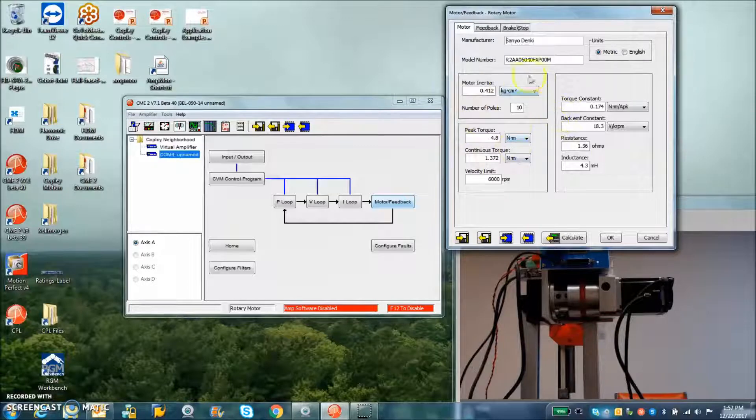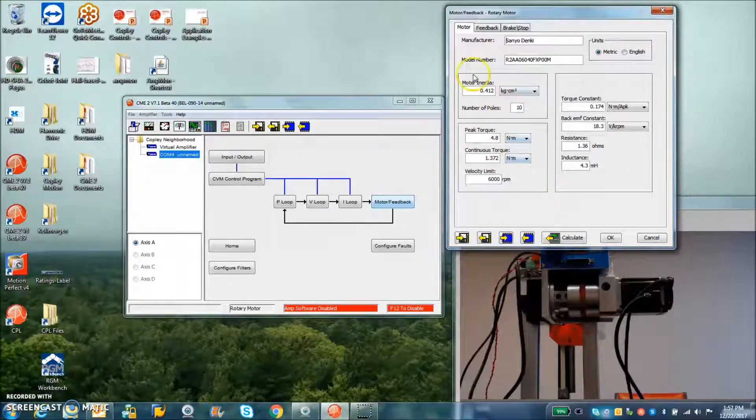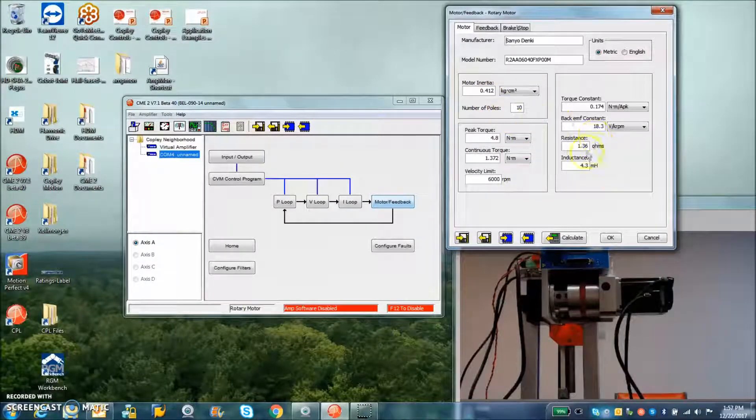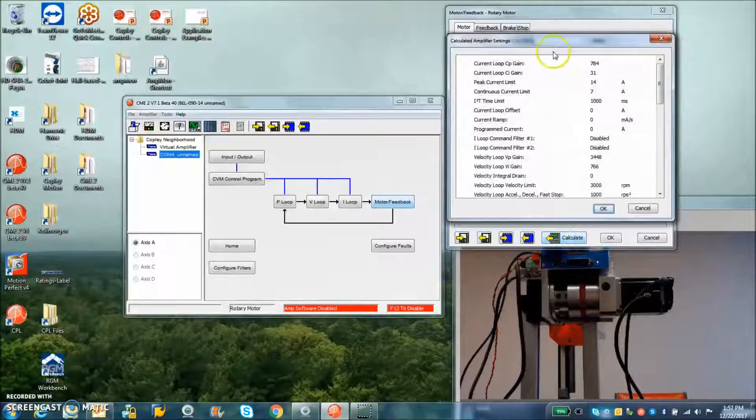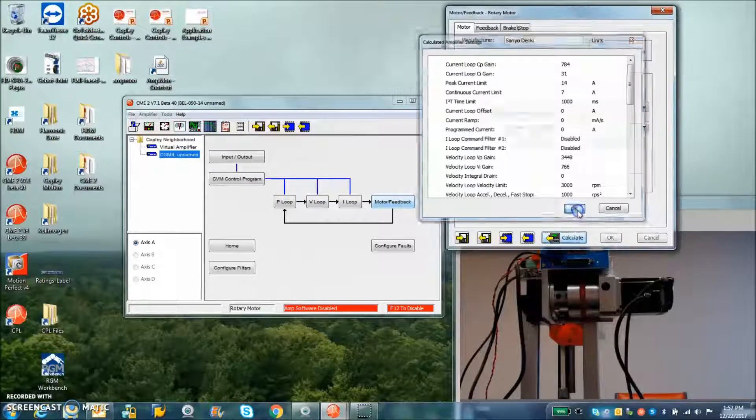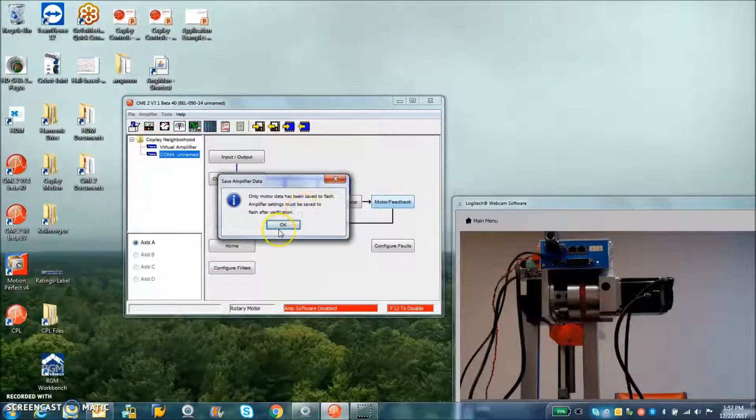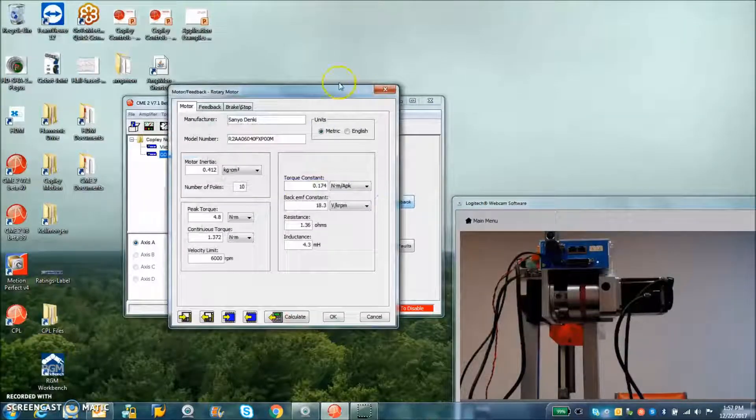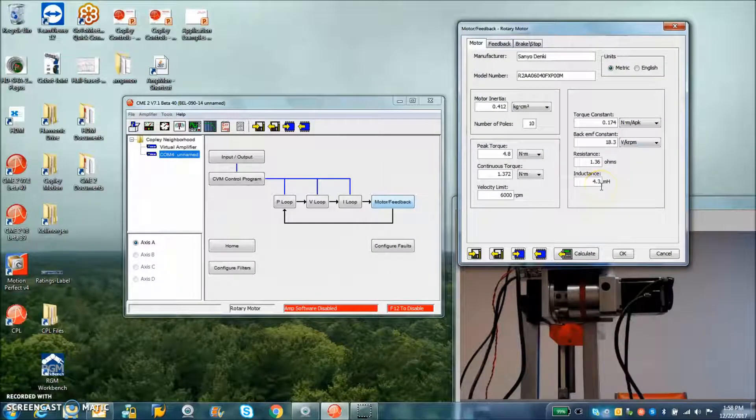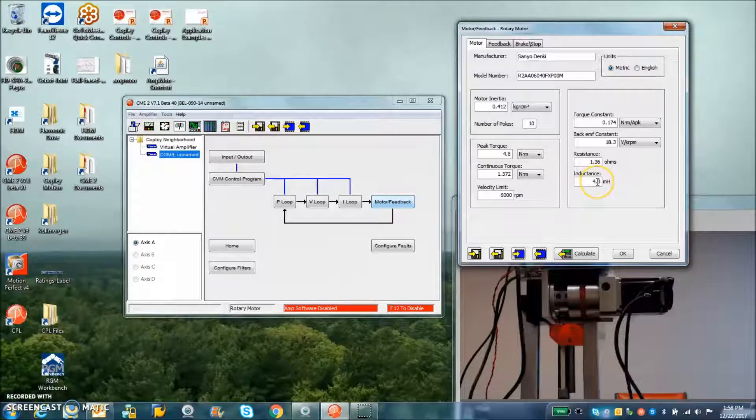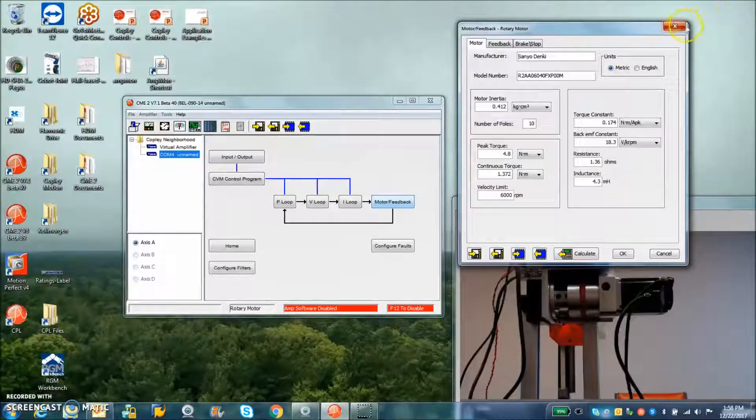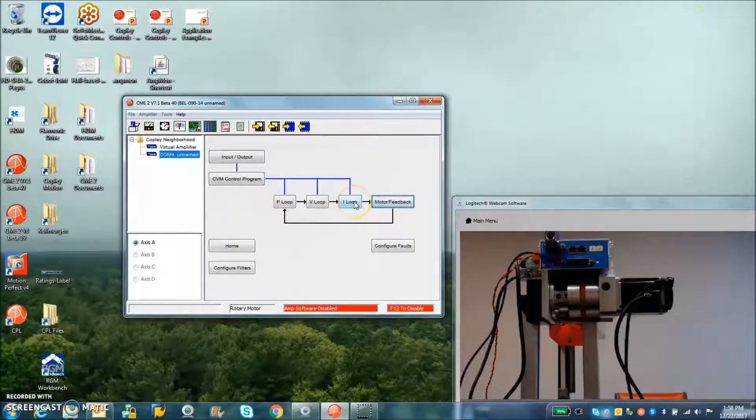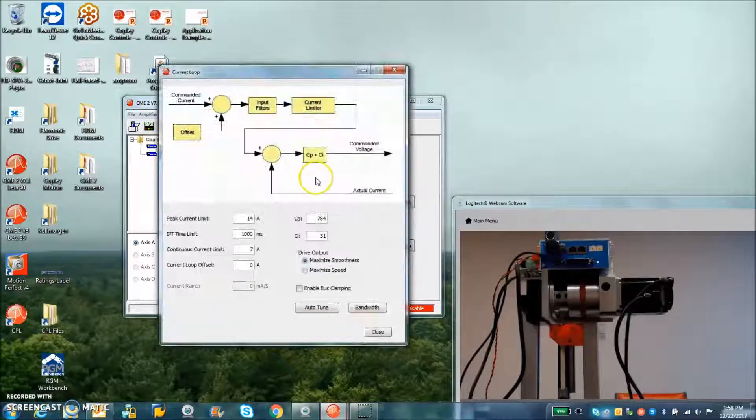So I started with Sanyo Denki motor data inertia. I didn't add the load inertia so I'm just working off the motor inertia. The values that originally are used here are calculated by a math model based on the data we input. So we get some pretty good values here. I may have a mistake with entering my data. Maybe it's 4.3 millihenry phase to neutral. Well, the inductance is phase to phase. So maybe it's really eight millihenry across the pair of wires. But that's okay. We're going to tune it. So we get some pretty good data. I get a pretty good calculate.